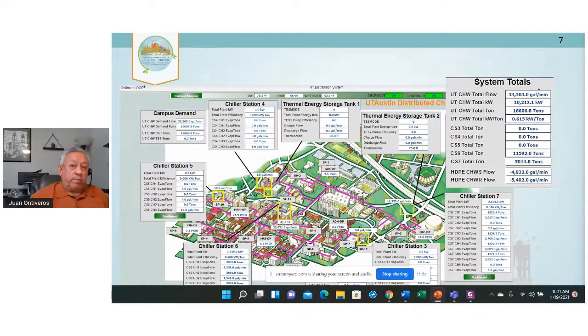7 is the newest one, and I'm going to show you later on a video of what that chilling station looks like. But the snapshot this day is a relatively cool day. It's 70 degrees, but we're producing 16,000 tons, 10,000 kilowatts, and 33,000 gallons a minute at this instant. We cool 24/7 all year round. Even in the winter, we have a cooling load because we have computer systems and labs throughout the campus. So at this particular snapshot, the total kilowatt per ton for the whole campus is 0.6.